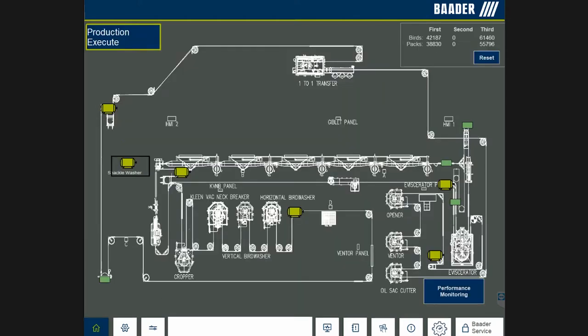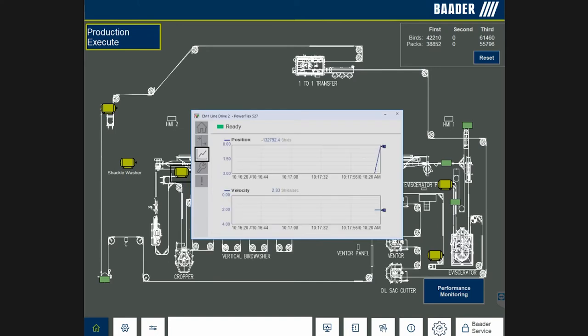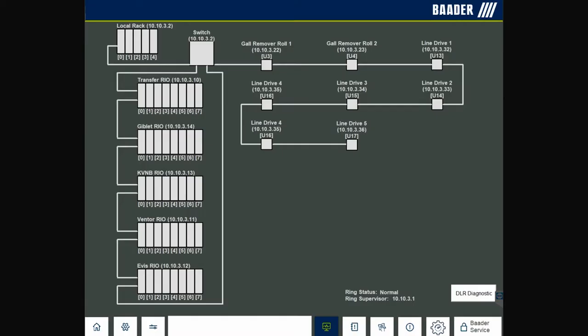By pushing the motor on the screen, you can easily see detailed technical information about a motor, such as velocity and a diagnosis. If a connection is broken within the DLR device level ring, a red flashing light will indicate where the break is located. The system will continue to function even though a connection is broken. As an added failsafe, a single broken connection will change the direction of the ring to keep the line operating.